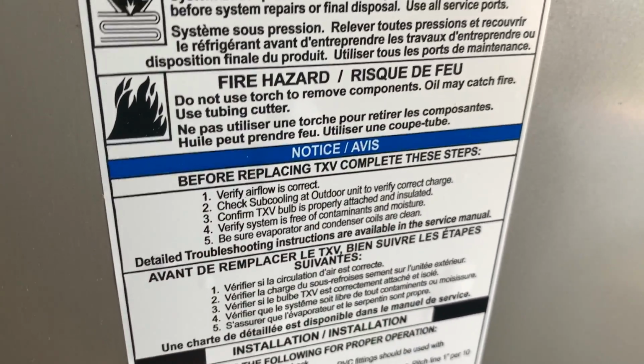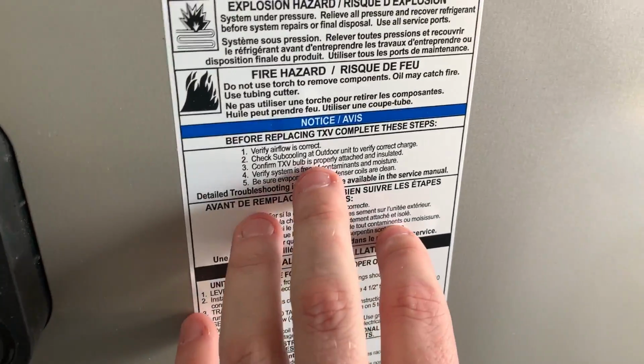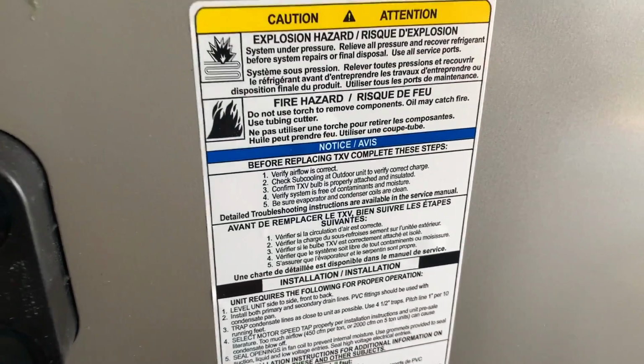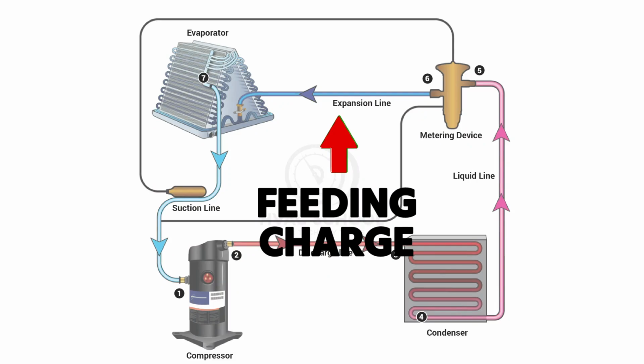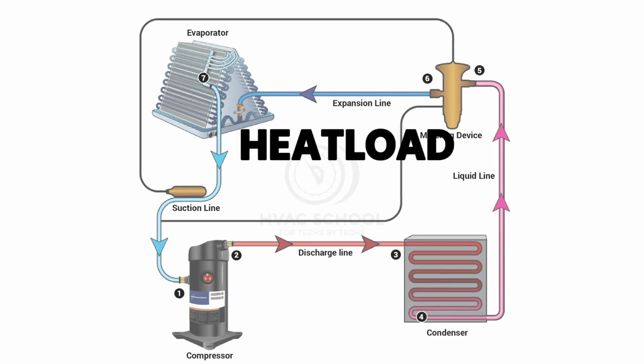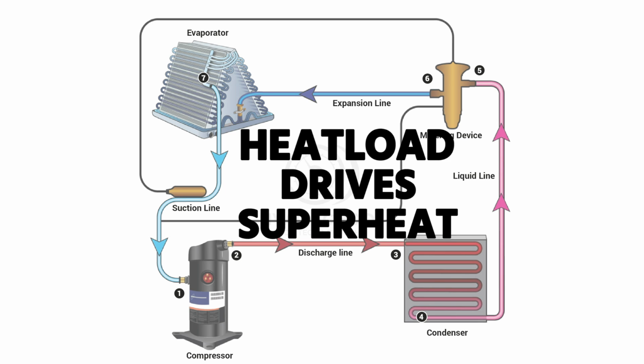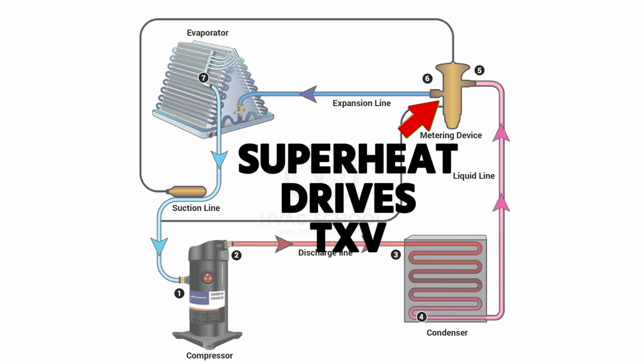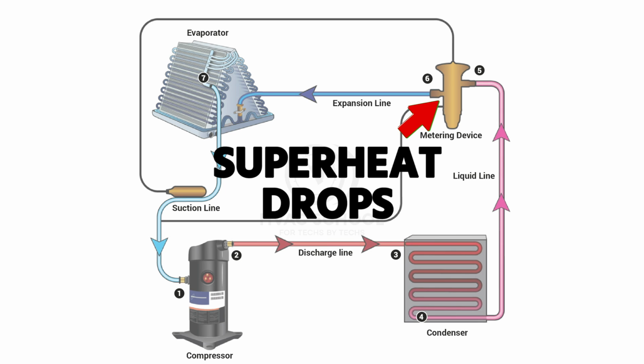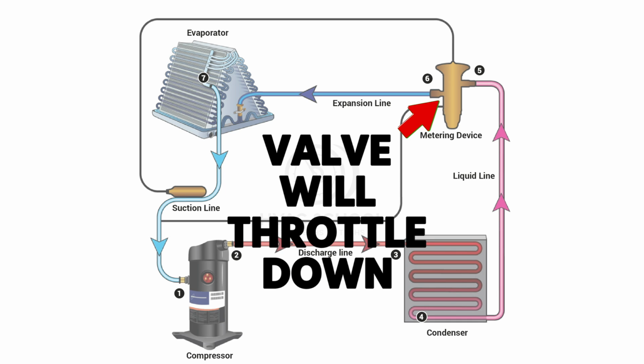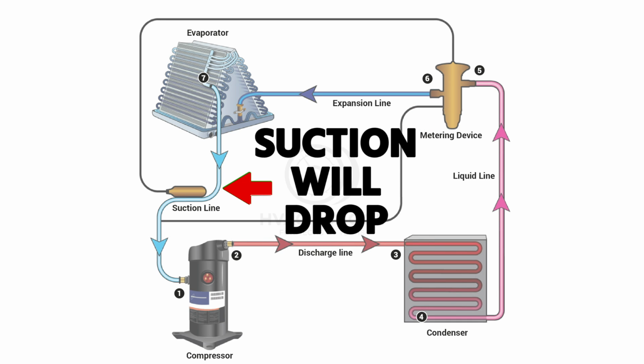So often the TXV gets blamed because people think of the TXV as being a valve that is responsible for feeding charge through the evaporator coil, but you keep in mind that heat load is such a big factor in what drives superheat, and superheat is what drives your TXV open and closed. When that superheat drops because of low airflow, that valve's going to throttle down and your suction's going to drop. It's not always the TXV.